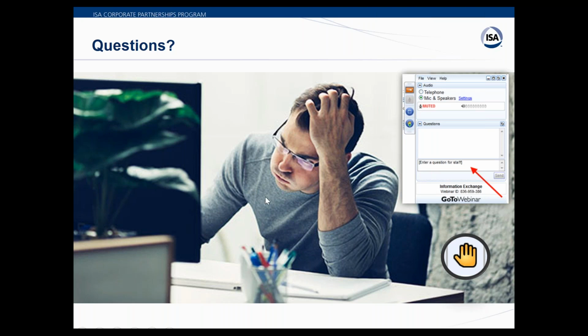Okay. Would you base calibrations on critical and non-critical systems? Well, the place to start is your critical ones. I think if you really focus on your critical instruments and measurements in your plant and get a calibration program going for those first, then what you learn and what you develop there can be easily applied to the non-critical, and you can expand out. And again, if they're non-critical, maybe you don't have to check them as often, so you can blend it into the work you're doing on the critical ones. Agreed.